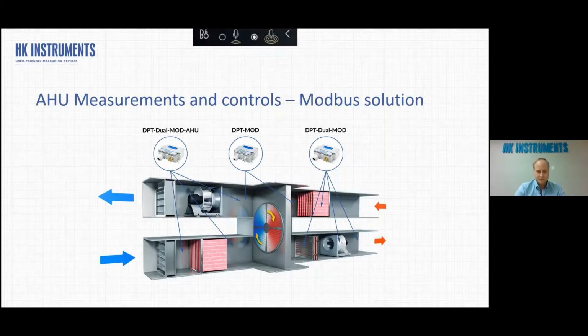The reason is that in our Modbus devices, we have been integrating this kind of I/O points also to these devices, which means that we can connect, for example, 2 passive temperature sensors to our DPT-Dual-MOD or DPT I/O mode. And with Dual-MOD, as the name says, it has 2 inbuilt pressure sensors. So you can get, for example, the fan pressure, and by that you can also get the airflow rate. But with the same device, you can get also differential pressure, for example, over the filter, and also 2 temperature sensors in addition. So basically what you can do is get 4 measurements to the bus by using 1 device.